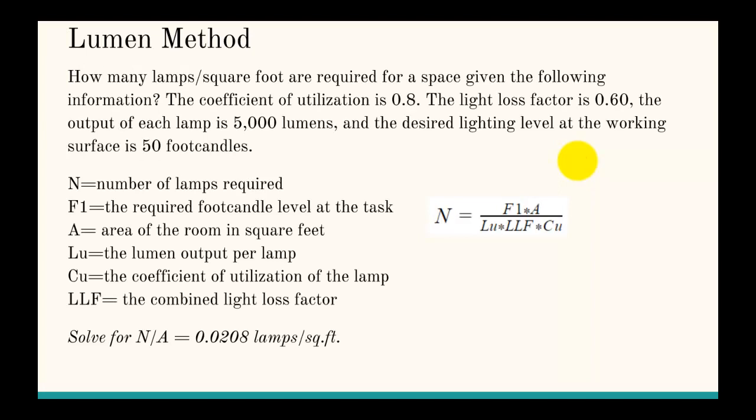Let's look at this problem. How many lamps per square foot are required for a space given the following information? The coefficient of utilization is 0.8, the light loss factor is 0.6, the output of each lamp is 5,000 lumens, and the desired lighting level at the working surface is 50 foot-candles.